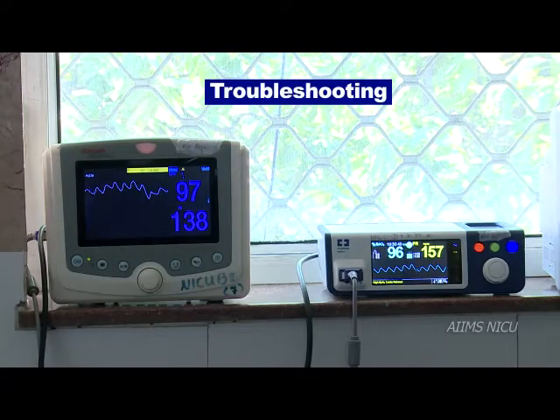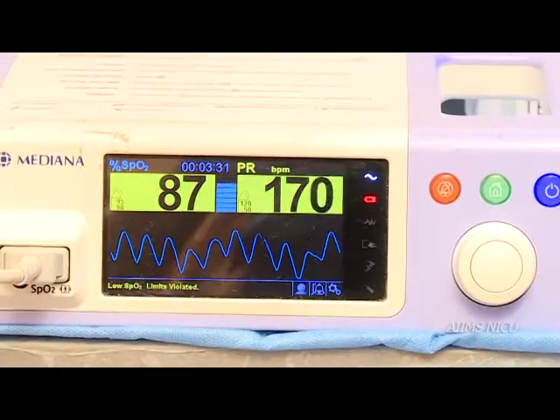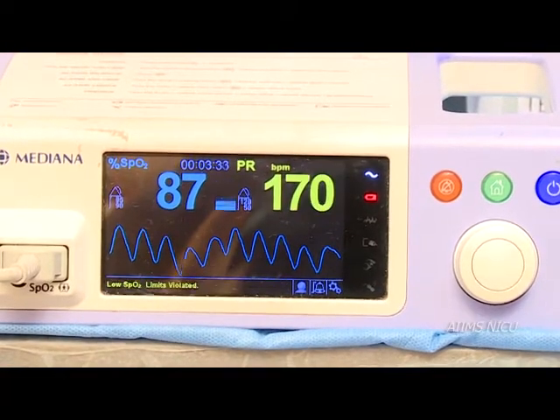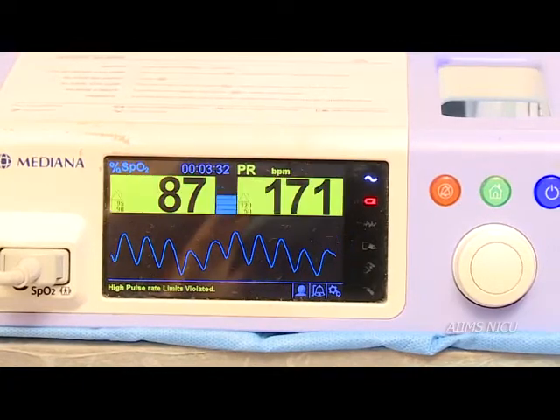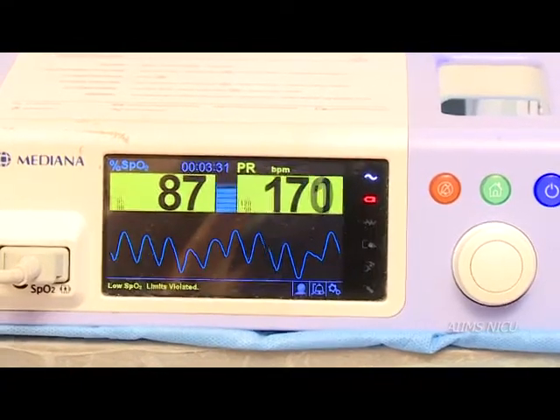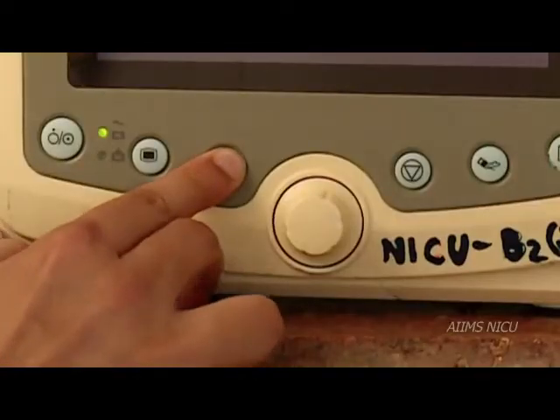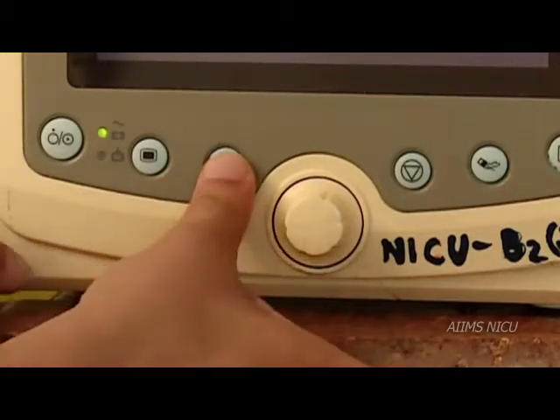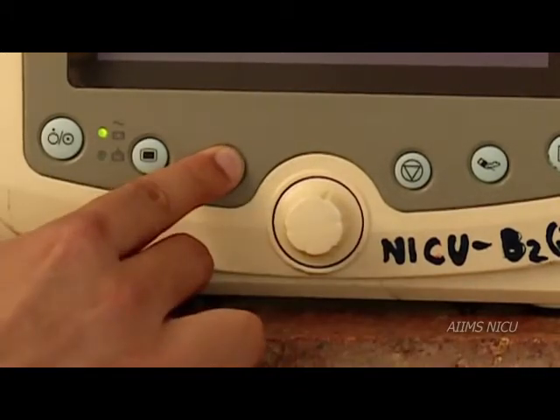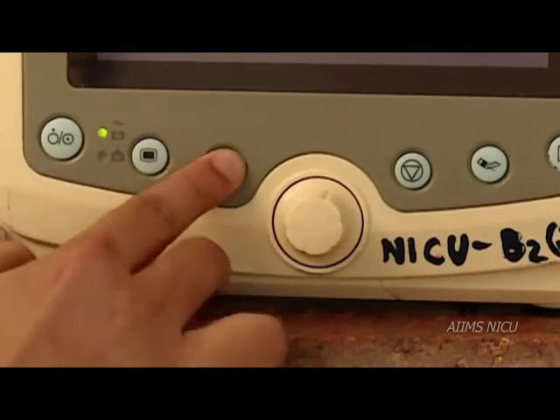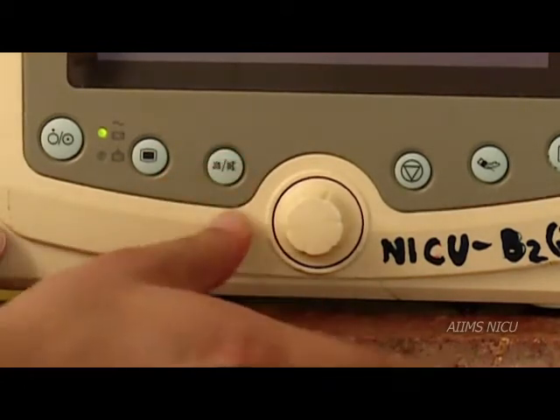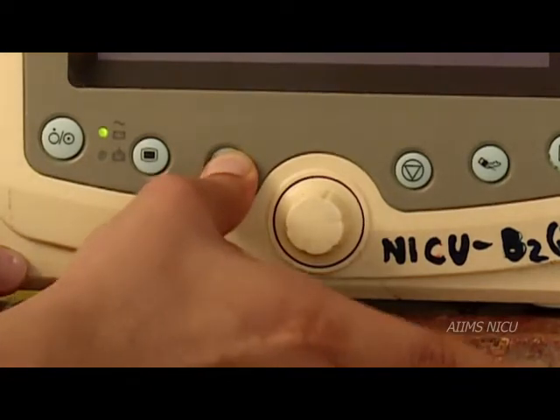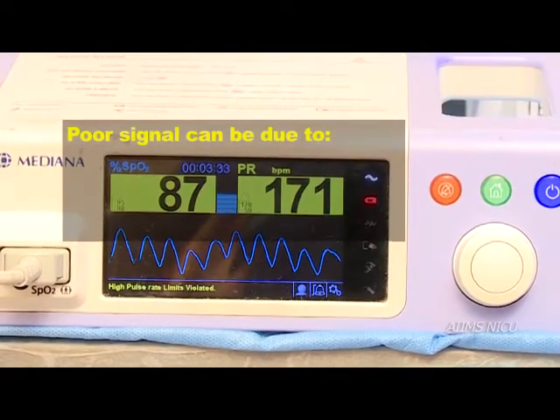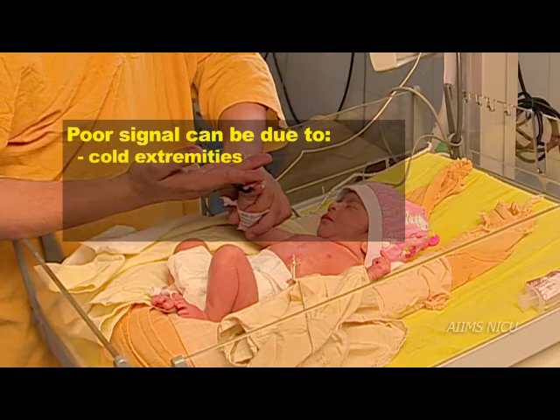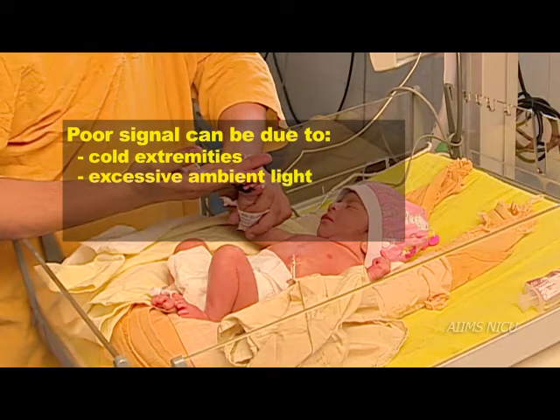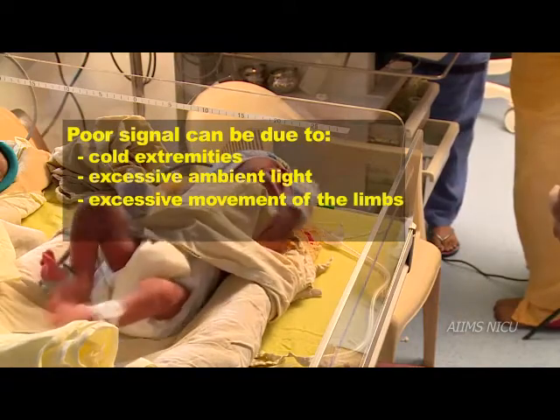Let us now try and understand some troubleshooting. In case of an alarm due to abnormally high or low oxygen saturation or heart rate, that is, beyond the set alarm limits, it can be muted by pressing the mute button. For a longer pause alarm, mute button can be pressed twice or thrice. Alarm, if any, can be visually identified. A poor signal can be due to cold extremities, excessive ambient light, excessive movement of the limbs, or low perfusion.